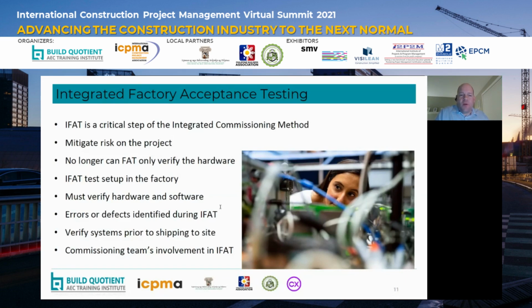In the past it would seem like a good idea to ship the hardware to site as soon as it's manufactured, to get it installed quickly and avoid delaying the project. But that old mindset doesn't work anymore—we need to account for an integrated system that includes the software in factory acceptance testing, and plan the project to allow time for that. Without the commissioning team's involvement, it would logically seem to make sense to get hardware to site as soon as possible, but in every instance I've seen on projects I've worked on, that has never worked out well.